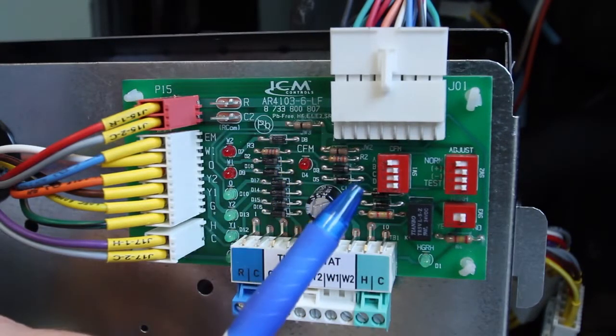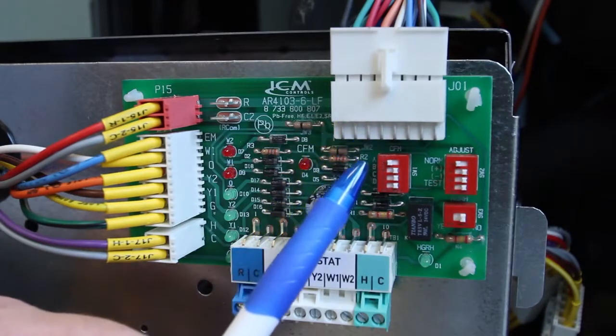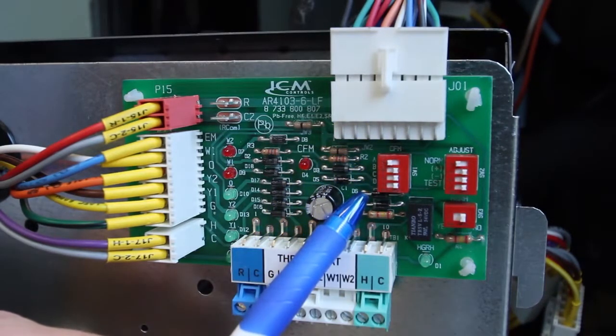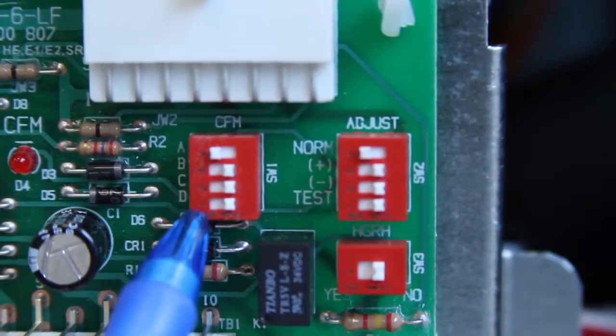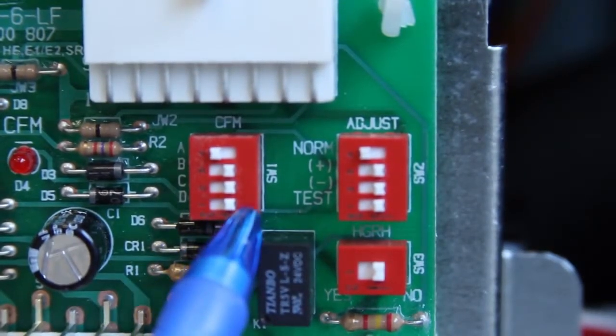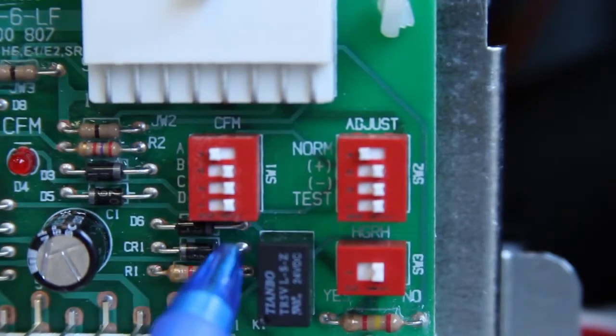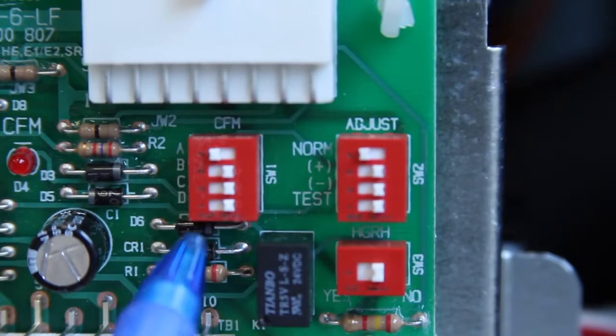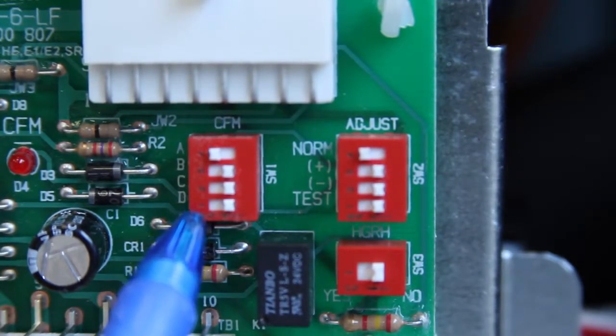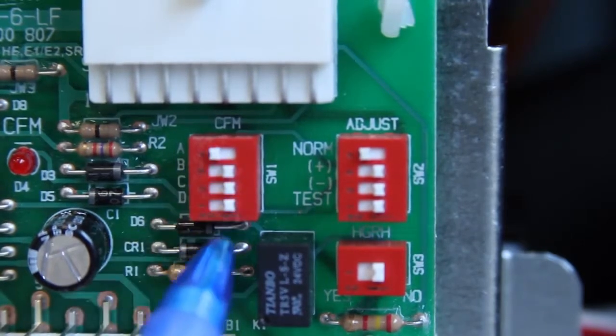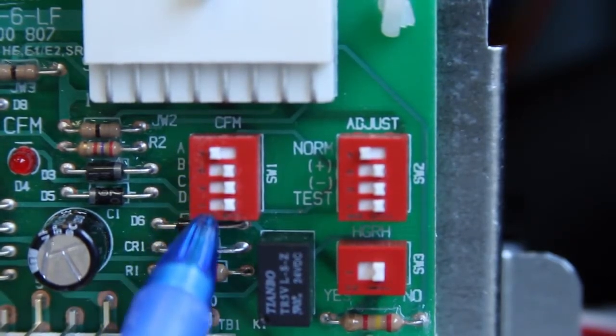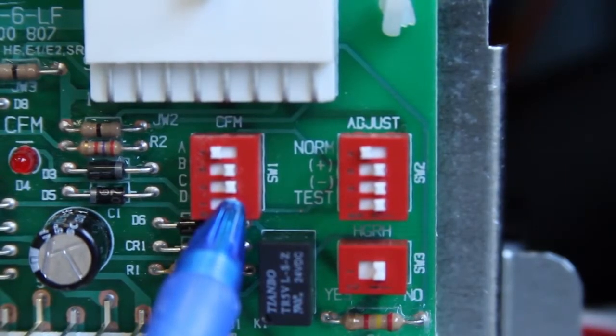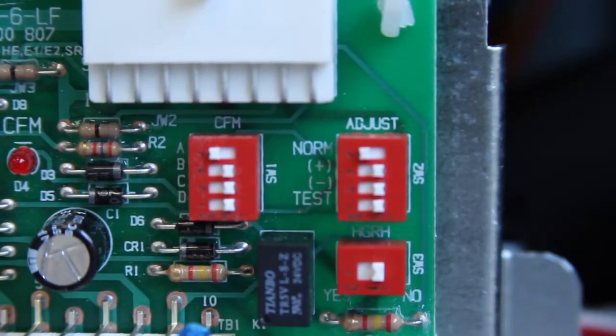Over to the right of the thermostat block, just below the 16-pin connector, is a set of dip switches labeled CFM. The on position is the left-hand position and the off position is the right-hand position. If you look at the blower tables on page 59 of the installation and maintenance manual, you can see that all of the SM models currently should be in the on position in position A. So dip switch A should be in the on position. Dip switches B, C, and D should be in the off position. But always consult the installation and maintenance manual for your model to make sure that is the correct positioning.